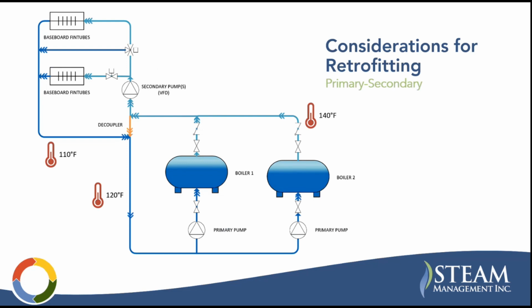So this is a primary-secondary system. Again, we're flowing through your primary loop and then pulling off of it for your secondary loop. You want to optimize your controls to reduce the flow through this decoupler. So maybe your primary pumps and secondary pumps are communicating. I don't want to say matching flow, because you still want to over-pump your primary loop compared to your secondary loop, but minimizing flow through this decoupler so that you get as little blending as possible. So you can see here a 110-degree return temperature would be great for the boilers, but we're blending with some amount of this 140-degree supply to get an actual return temperature at the boilers of 120 degrees. Still in condensing mode, but if you were to look back at that curve, decreasing your efficiency a little bit.